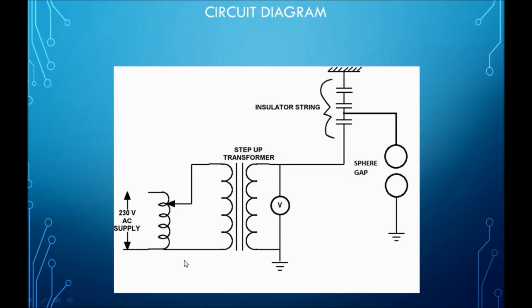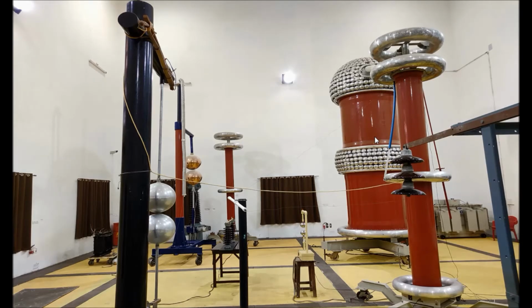Finally, the calculation part. This is the main transformer or high voltage transformer, and this is the measuring capacitor. You can measure the high voltage through this capacitor. And this is the string. You can see the three disc insulators connected here, and this is the spark gap. The top point of the spark gap is connected with a yellow wire, and this yellow wire is connected to this point, which is the output point of the transformer.